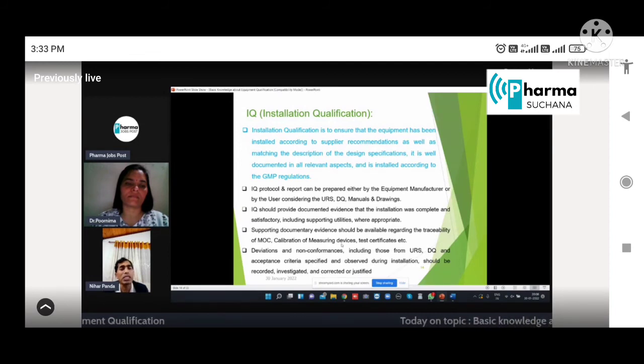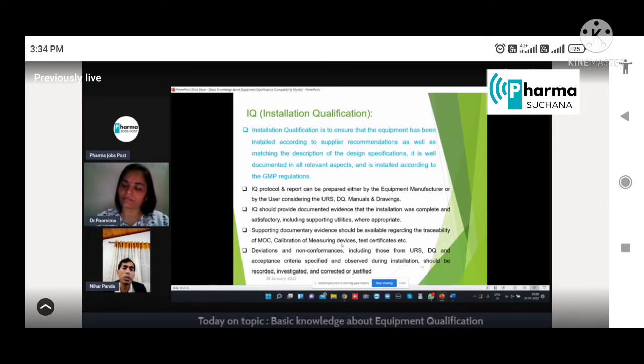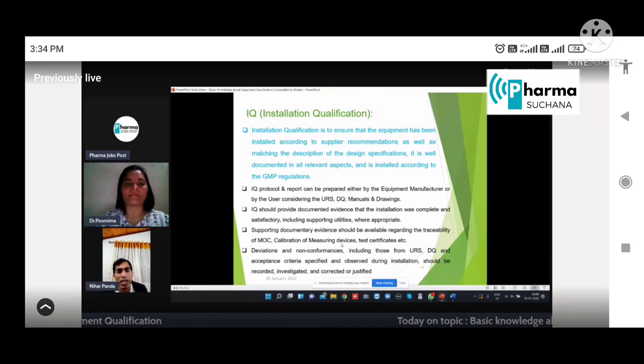Other test certificates, meaning hydro test certificates and other parameter test certificates, they should also provide. Then if any deviation is there during the installation, as per the feasibility, some discrepancies may be there. Those things need to be written in a prescribed document, that is your deviation document, including those from URS, DQ, and acceptance criteria specified and observed during installation. If any deviation is there, it should be recorded, investigated, and corrected with justification.